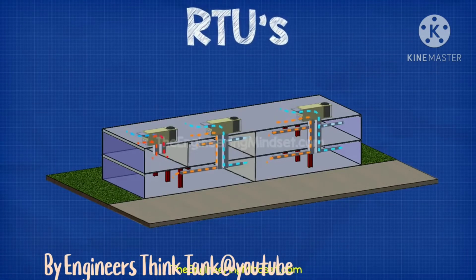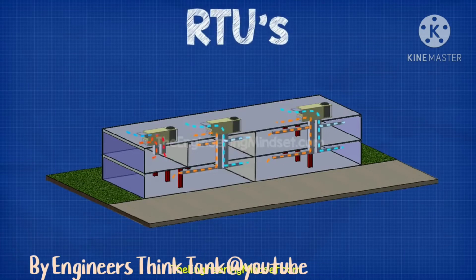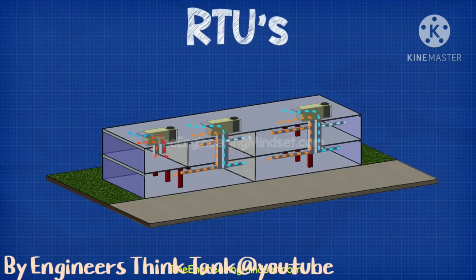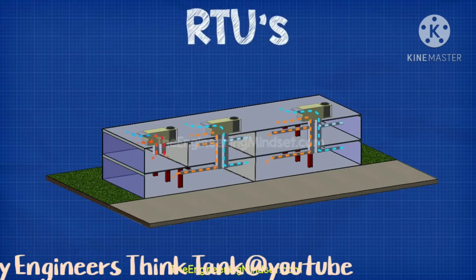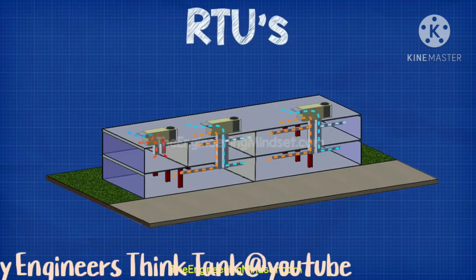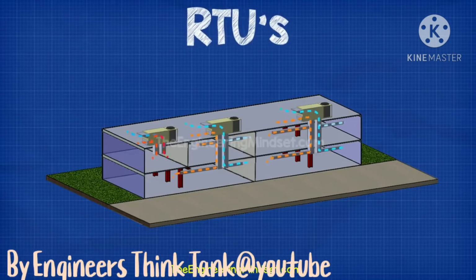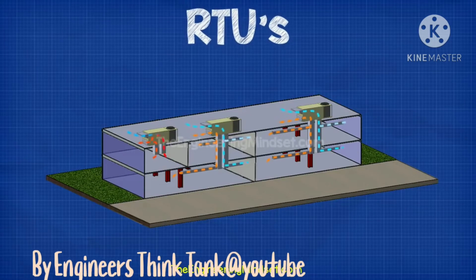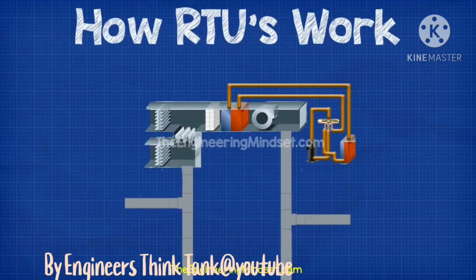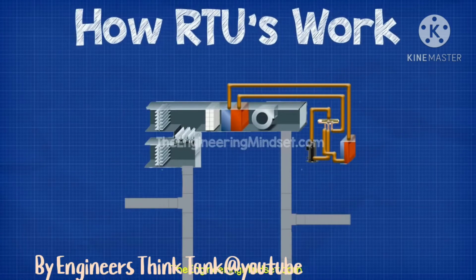RTUs are also connected to ductwork, which provides a defined route for the conditioned air to travel along. RTUs typically have their own inbuilt refrigeration system to provide cooling only, but they can also contain a heat source such as a gas-fired heater or an all-electric heat pump. RTUs house all the components within the rooftop unit.